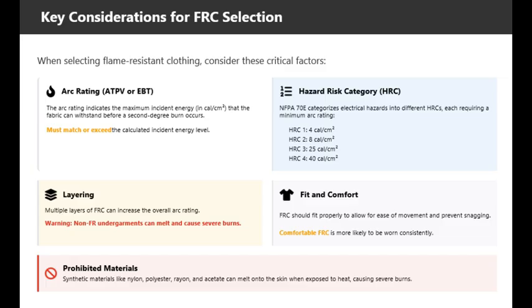Next is the hazard risk category or HRC, as defined by NFPA 70E. The standard categorizes electrical hazards into different HRCs, each requiring a minimum arc rating. HRC 1 requires 4 calories per square centimeter, HRC 2 requires 8 calories per square centimeter, HRC 3 requires 25 calories per square centimeter, and HRC 4 requires 40 calories per square centimeter.